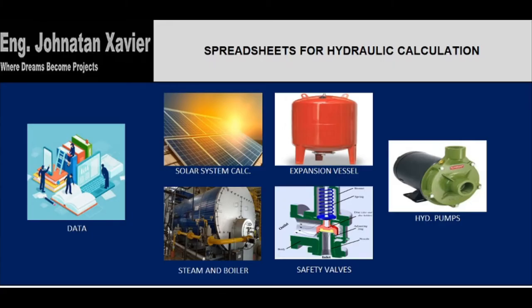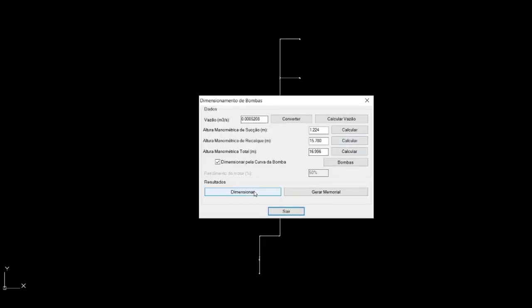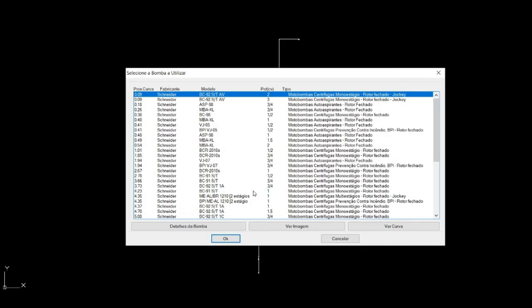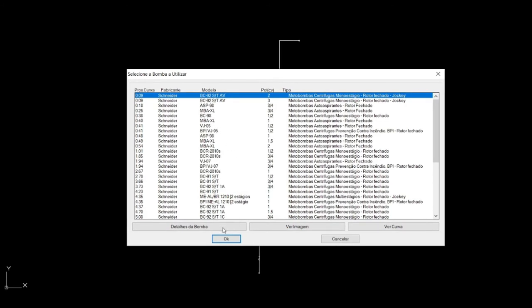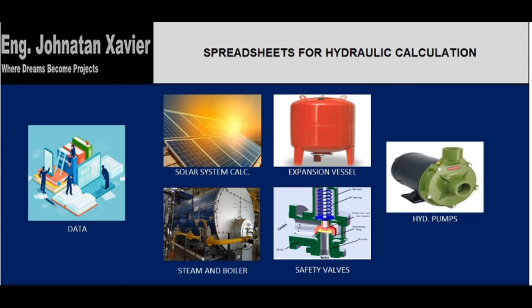For sizing of pumps, is also used the CAD plugin for the purpose of the calculation as shown here. To verify the line and to get the results, we just need to insert properly the information required. Just to gain time, I had inserted already, and I will just get the results. It will give me a list of pumps, that I can use in this system. At the end, I can have the results also in the document with the pump curve.